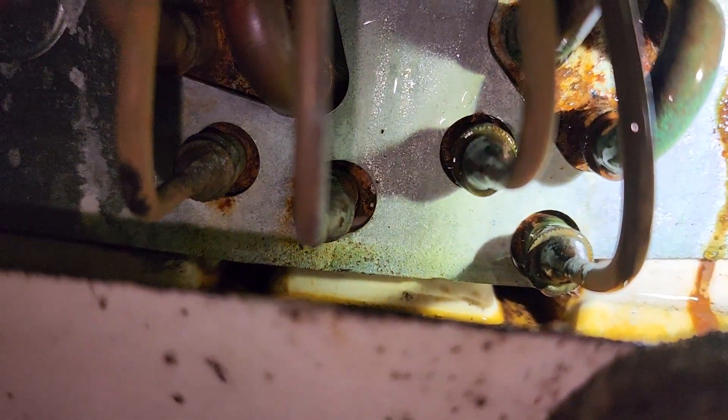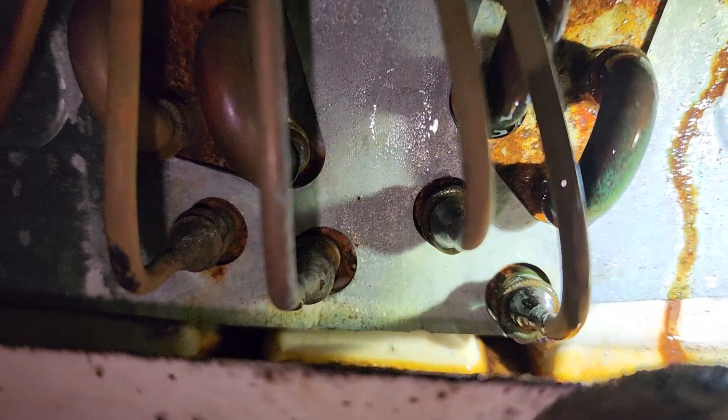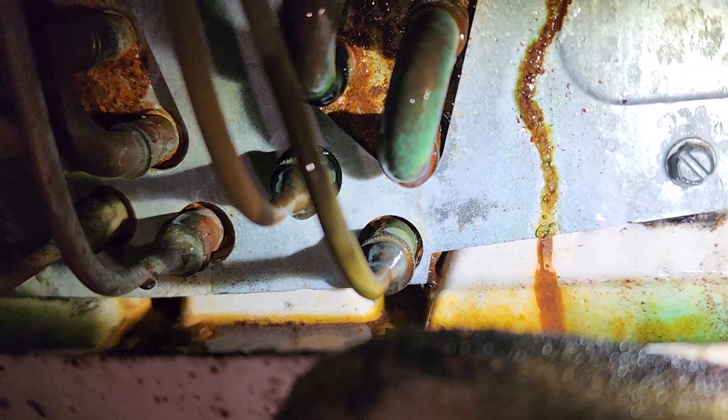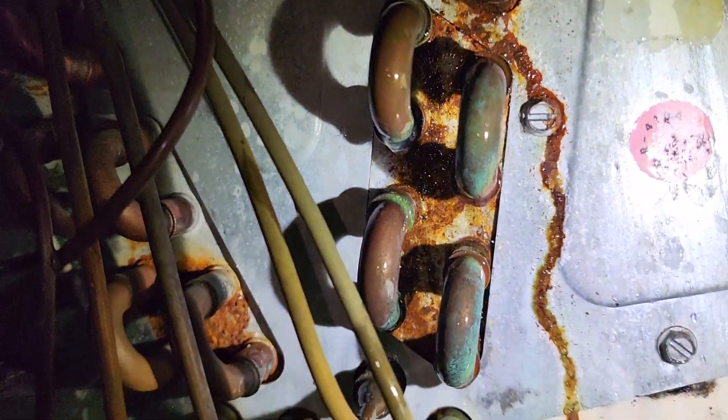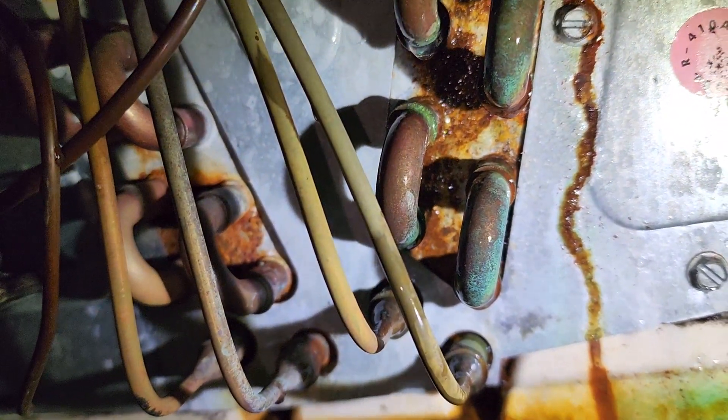It's not going to focus on it, but all the way behind that metal sheet. So that's not going to be easily repairable and I have a feeling there's probably multiple leaks on this coil. So I'm going to call and see if we can get a direct replacement coil to swap it out. I ordered that coil and put them in the schedule — I'll be replacing it Friday, early in the morning.